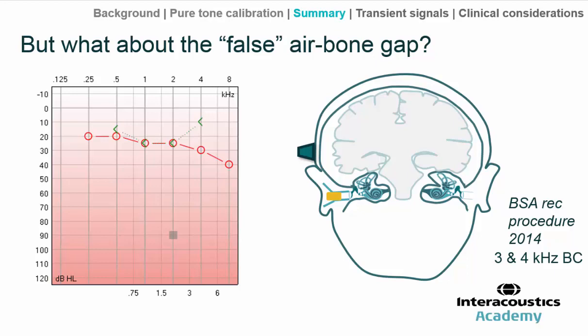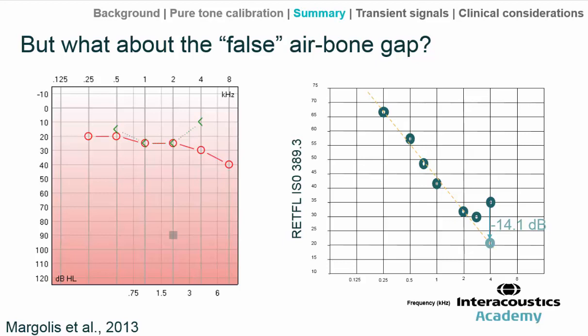So what might be the explanation? I'll refer you to this fascinating study by Margolis and others in 2013, which has really helped shed a lot of light on the situation. What these audiologists did was show the way in which the reference equivalent threshold force levels drop in a linear way as we increase in frequency. On the right side of the chart, frequencies are shown on the x-axis and the reference equivalent threshold force levels as published in the ISO standard on the y-axis.